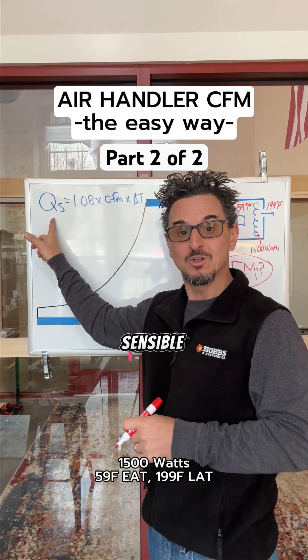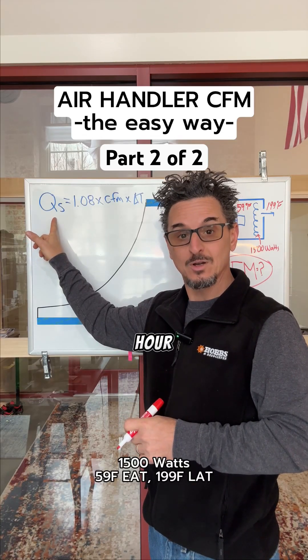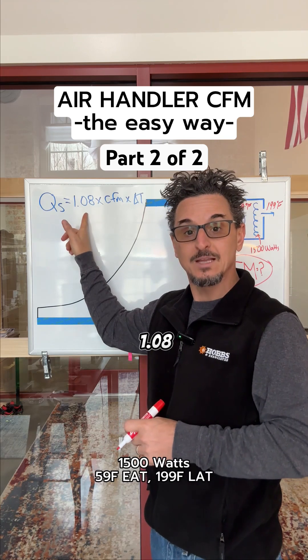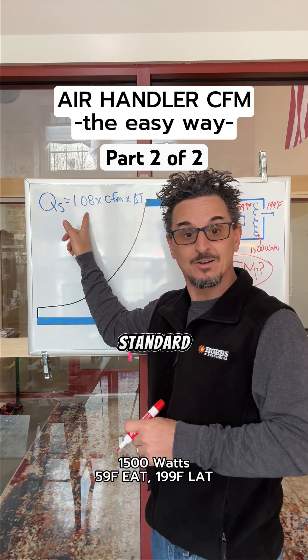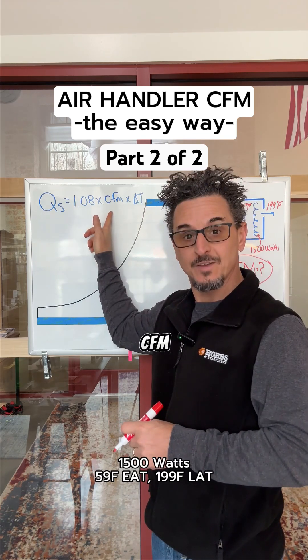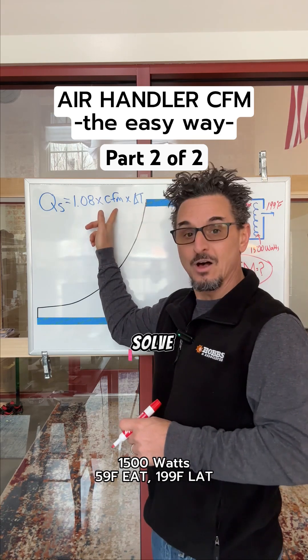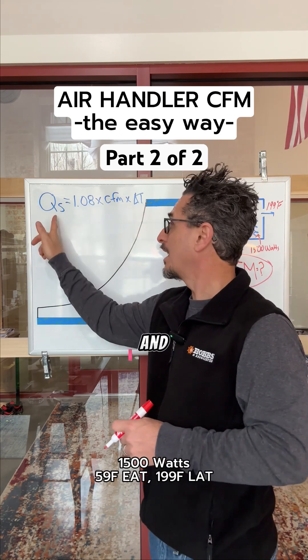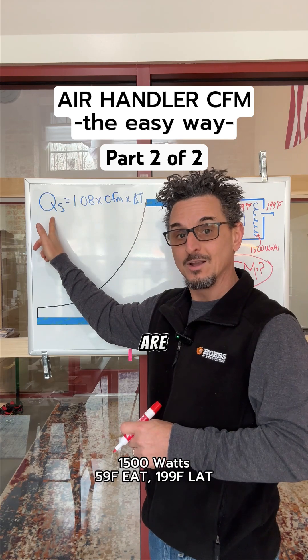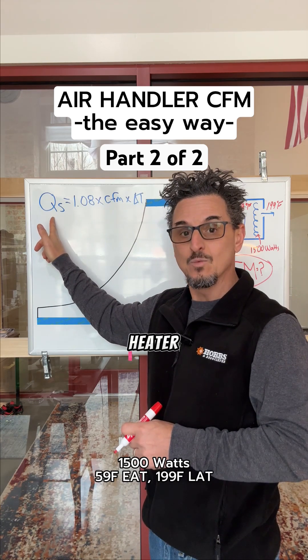QS is the sensible heat, or the BTUs per hour, which equals 1.08 at standard air conditions at sea level, times CFM, times delta T. We're going to solve for CFM and determine what the BTUs per hour are from the electric heater wattage.